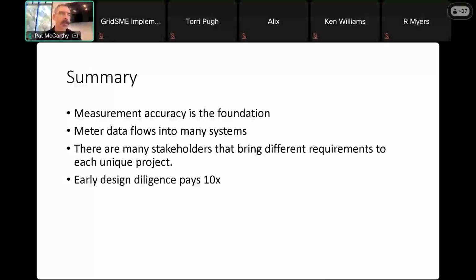actual accuracy of measurement, and that comes down to instrument transformer placement, ratio calculation, burden testing, device selection, verification testing. That's the foundation of everything. That meter data is going to flow into a lot of systems. I didn't really hit this very much, unfortunately, in this presentation, but places that data flows, I mentioned, it's the starting point for your closed loop controls for power plant controls. It can populate your SCADA system or your monitoring platform.